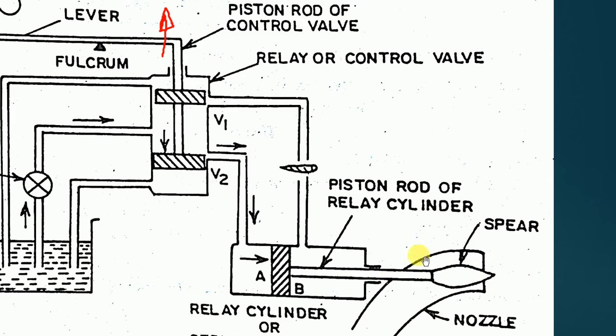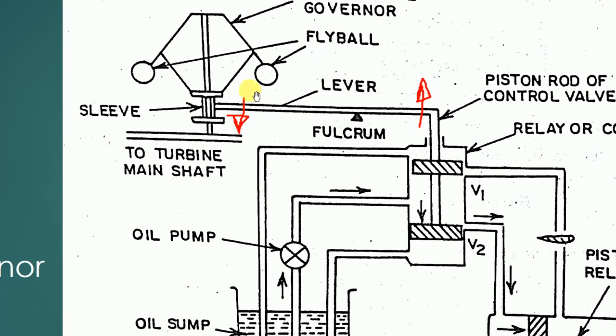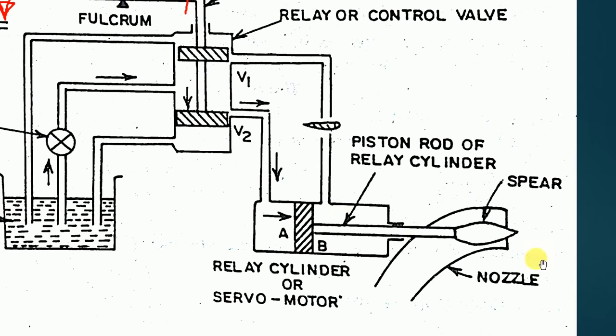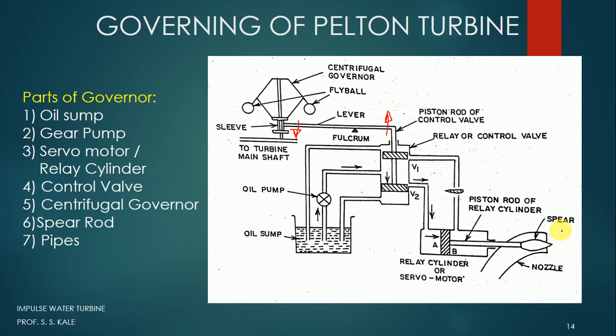As the spear comes back out of the nozzle, more area is available for the flow of water, so more water comes out from the nozzle and impacts the turbine. The turbine speed then increases. So as the speed reduced, the lever adjusted, oil came through V1, the spear came back, the amount of water increased, and the turbine speed increased back toward the set point.